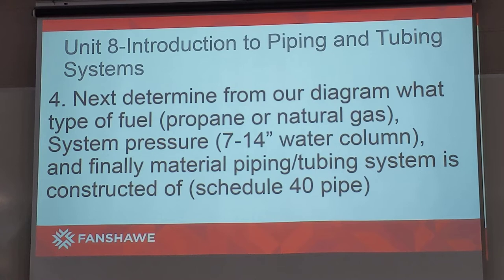We need to determine which table to use. The first thing we need to determine is what type of fuel we're using — propane or natural gas. Next, the system pressure; in this case we're looking at 7 to 14 inches water column of natural gas. And finally, what material the piping or tubing system is constructed of. In this particular case, the whole example is constructed of schedule 40 pipe.